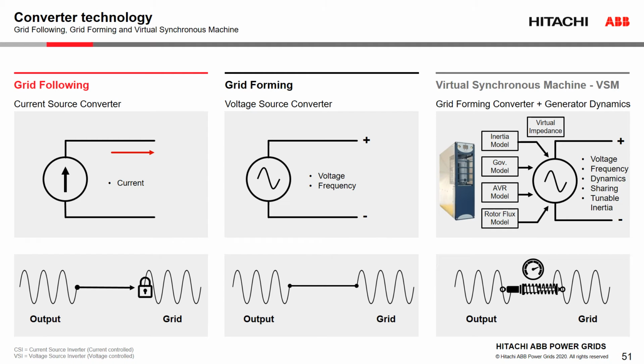Without this critical layer, you do not get the dynamic behavior from a grid-forming inverter that is conducive to operating on a network. It allows the voltage, frequency, dynamics, sharing, and inertia to be tunable. So the key factors of grid forming and virtual synchronous machines are they do not have phase lock loops. They cannot be compromised if the grid condition is affected.